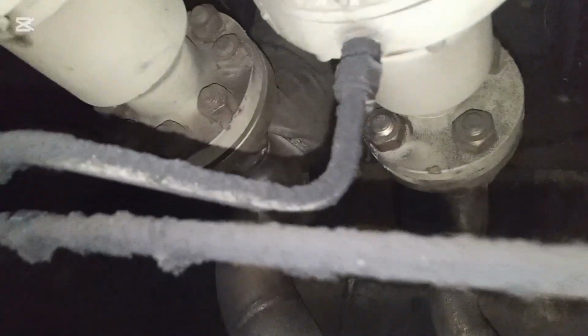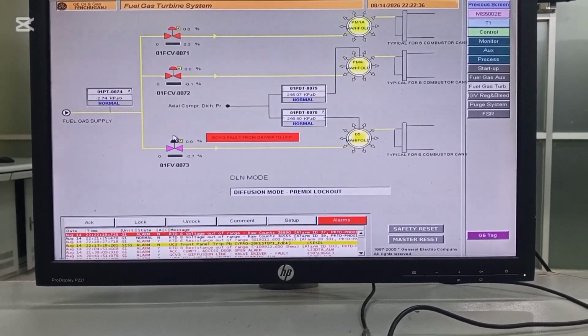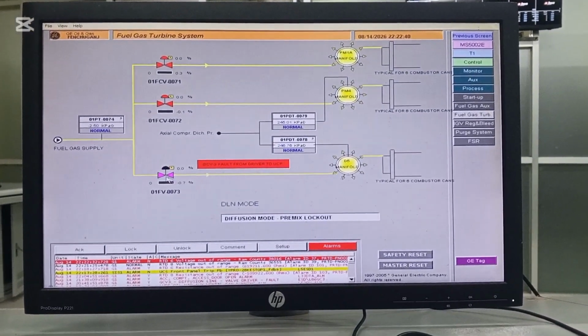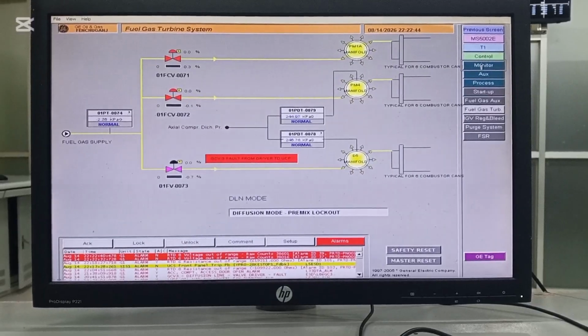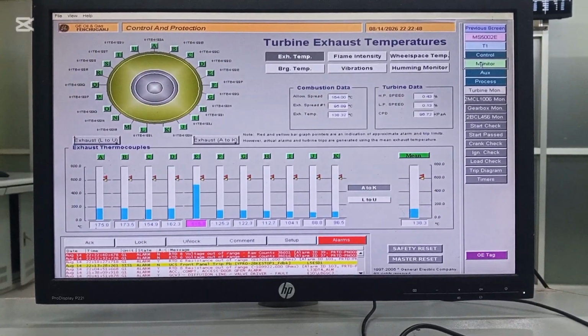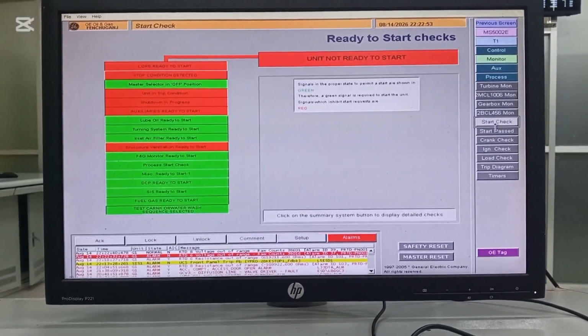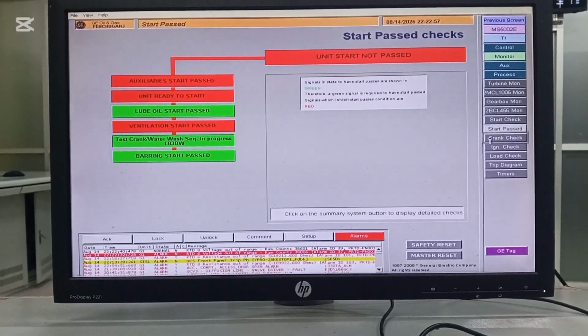Maybe it is a valve problem, but we saw that the driver unit is not functioning properly, and the problem is controller related, driver unit related. So after checking the motor operated valve air connection line, we opened the motor drive controller unit. This is the fault. The display is just flickering between pink color and black, and the alarm is showing here. We also saw the different parameters of the gas control valve at this faulty position, and here is some alarm.